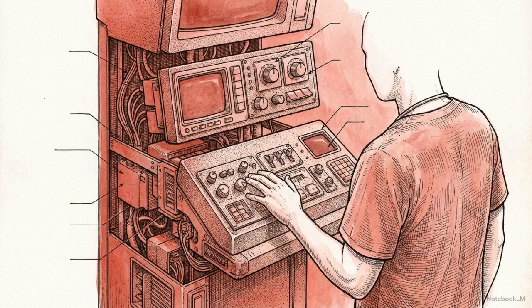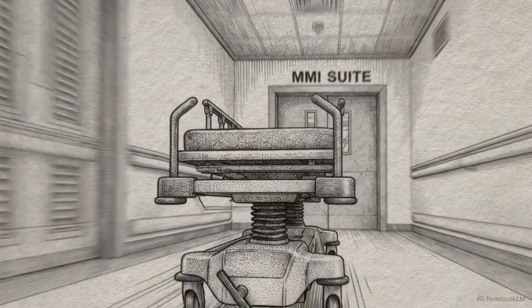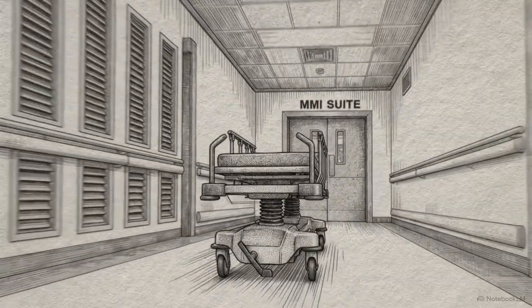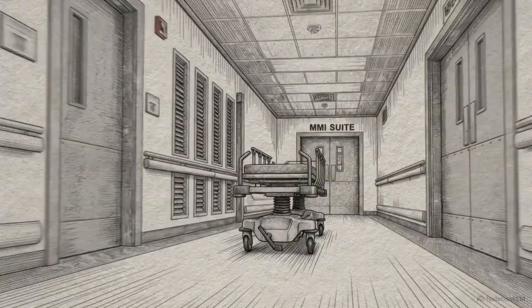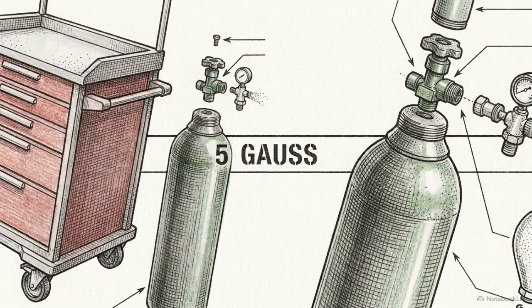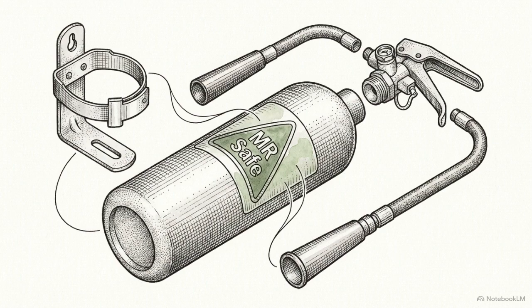Gradient fields interact with the electrical nature of the nervous system, requiring strict adherence to ICNIRP thresholds to prevent sensory and physical disruption. During a medical emergency, the physics of the MR environment override standard resuscitation protocols. If a patient suffers cardiac arrest, they must be moved to an MR-compatible trolley and taken outside the 5 Gauss line before treatment can begin. Ferromagnetic crash carts, oxygen cylinders, and defibrillators cannot be brought near the magnet, as the static field will pull them toward the bore. Fire protocols require the use of non-ferrous carbon dioxide extinguishers, which must be kept at a distance of at least 1 meter from the bore.